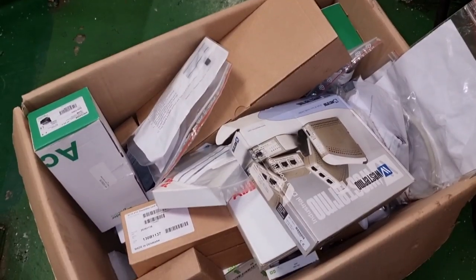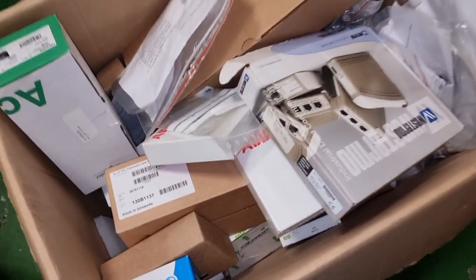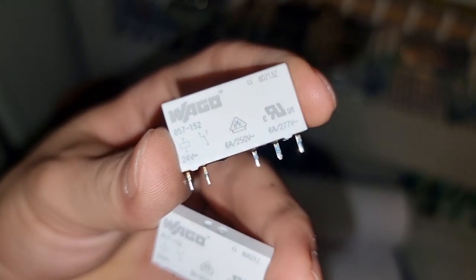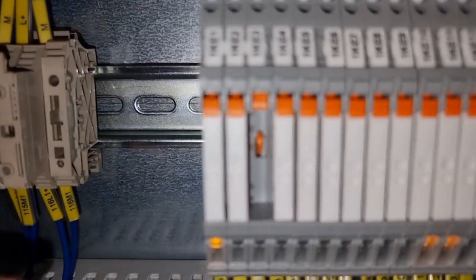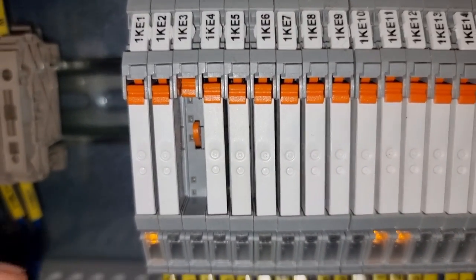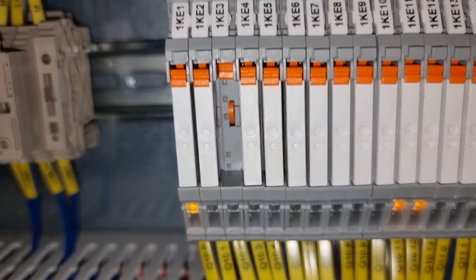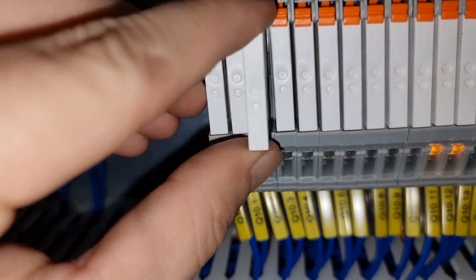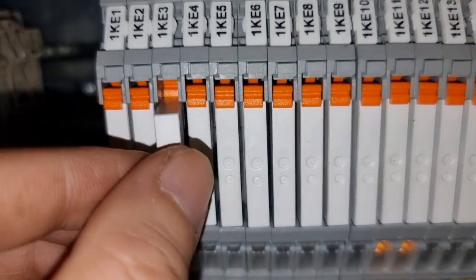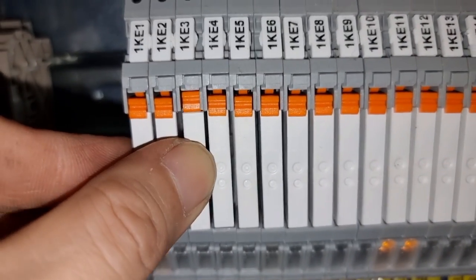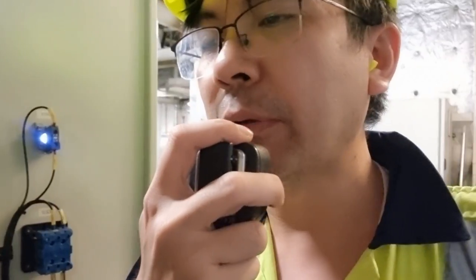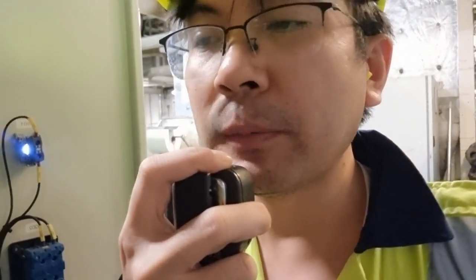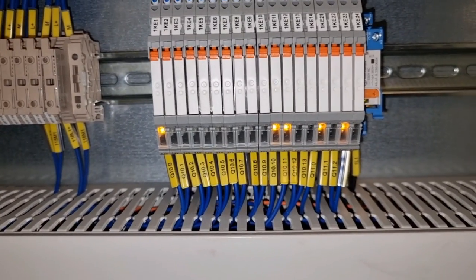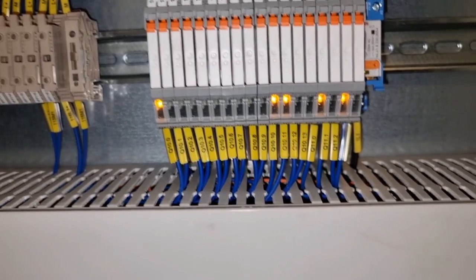So luckily, when I checked our boxes, I found one spare specifically for this one, and we just need to install the replacement and try it again to see if our valve will respond after replacing this relay. Just make sure that you have the proper orientation of this relay so that you will not bend the pin on this one. And then I called back the second engineer and tested it again.